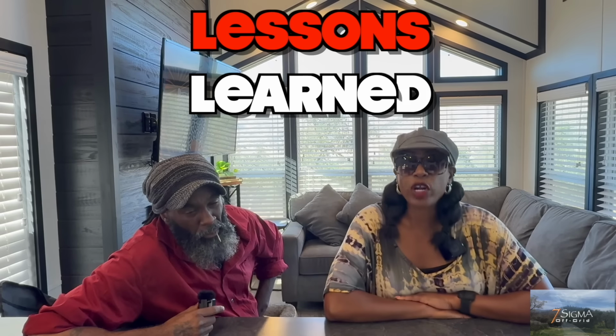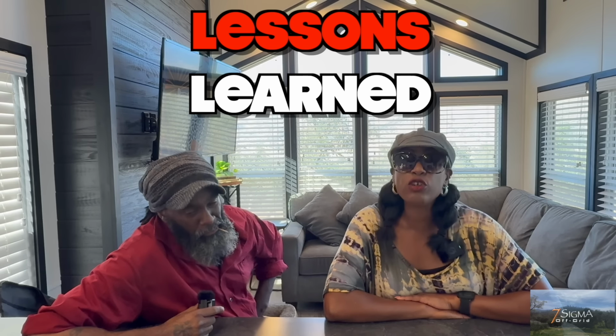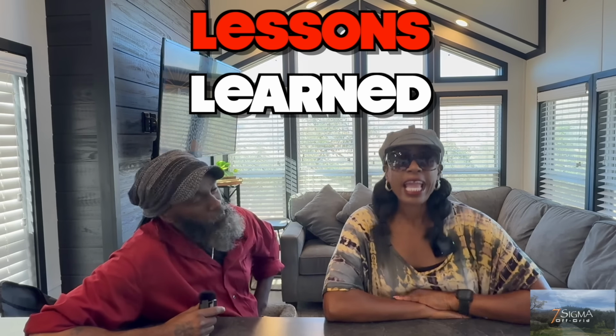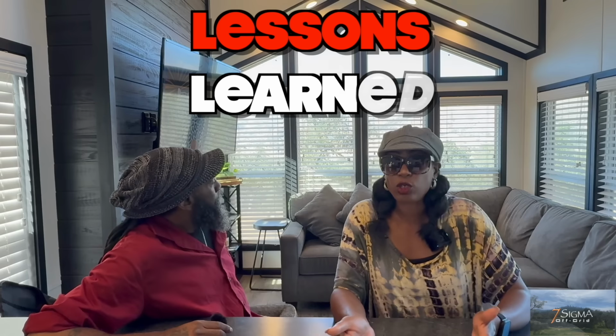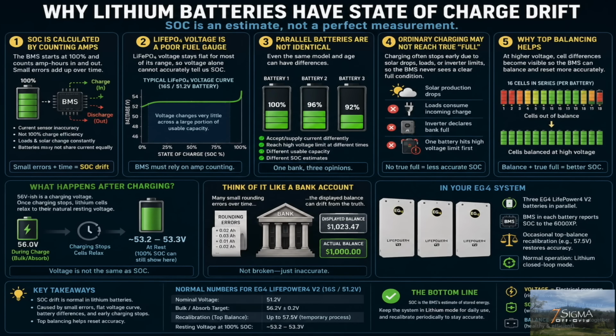So for a 48 volt lithium battery reading, 52 volts is not truly full, even if the dashboard says it's 99 to 100%. State of charge drift is common on lithium battery banks that are kept near full and never deep cycled. The percentage and the real capacity slowly fall out of sync over time.